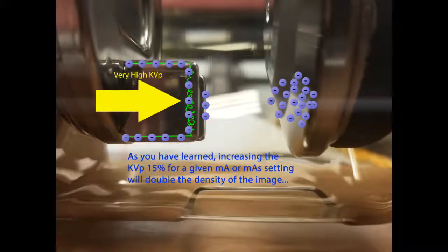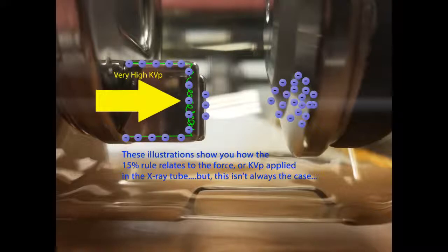As you have learned, increasing the KVP 15% for a given mA or mAs setting will double the density of the image. These illustrations show you how the 15% rule relates to the force, or KVP, applied in the x-ray tube, but this isn't always the case.